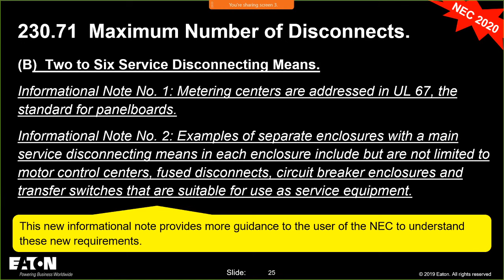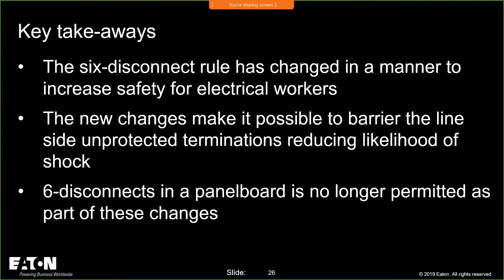With these changes, it's now possible to put barriers on the line side of those terminations. The key thing is if you are using six disconnects in a panel board, you're no longer permitted to do that as part of these changes.